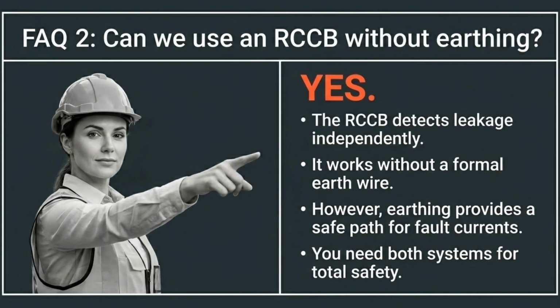FAQ 2. Can we use an RCCB without earthing? Yes, an RCCB detects leakage independently, even without a formal earth wire. However, for total safety, you need both the RCCB and proper earthing.